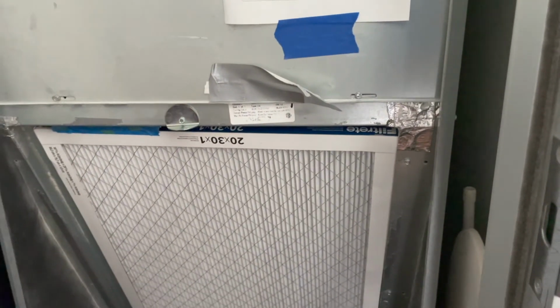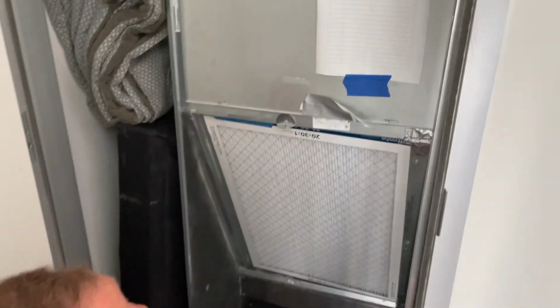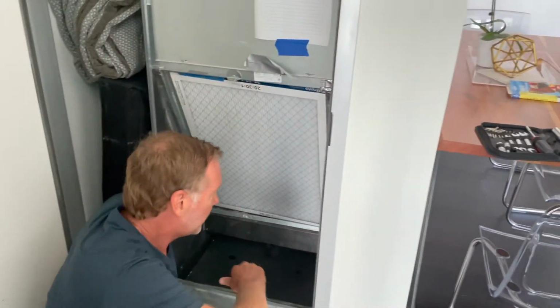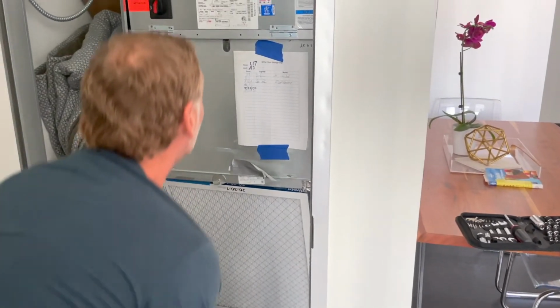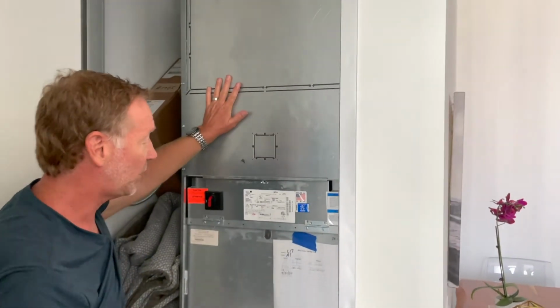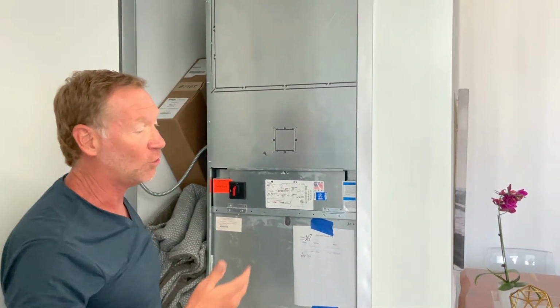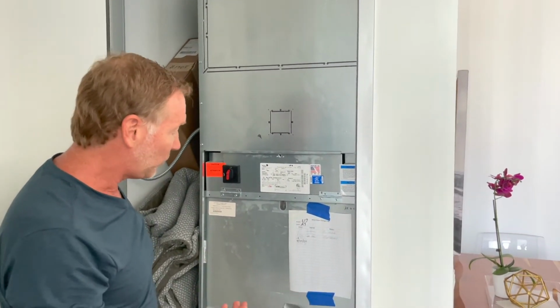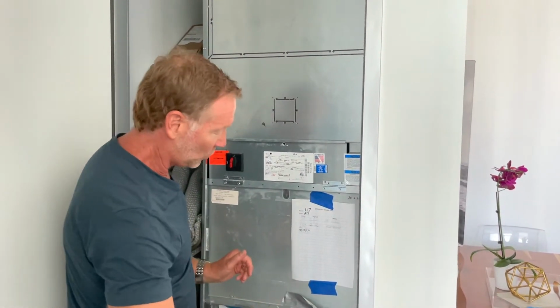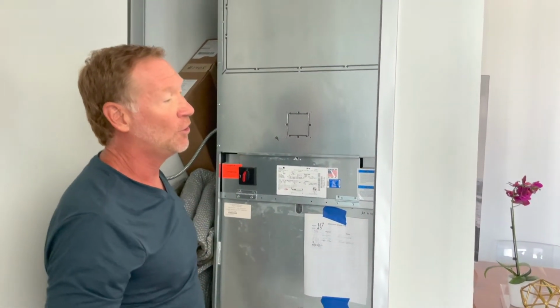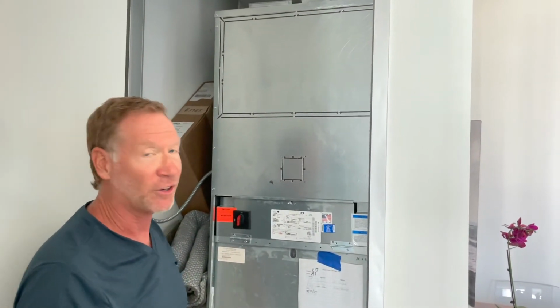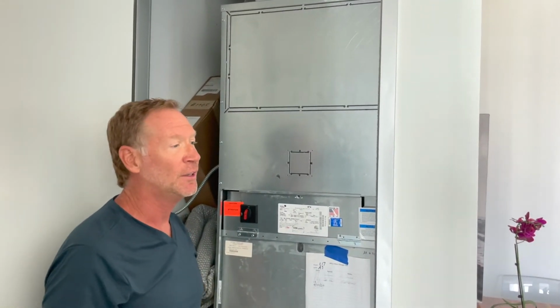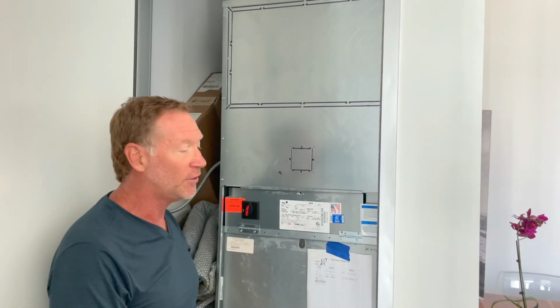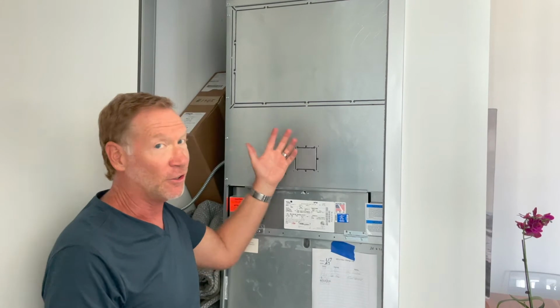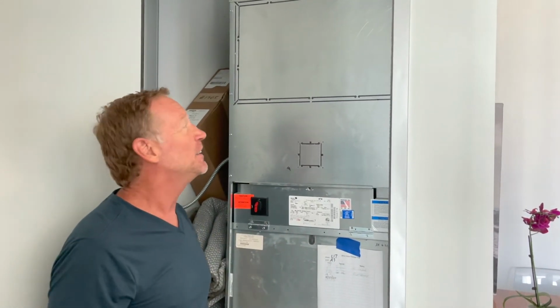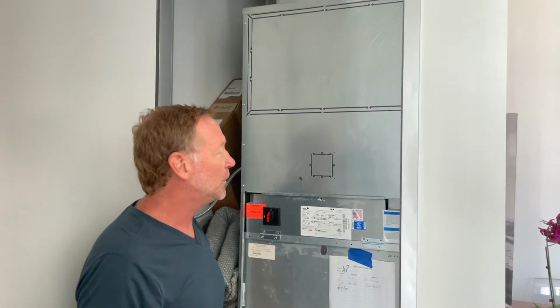The other thing a technician would do is measure differentials. Differentials mean how cold the air being produced is on the supply side versus the temperature going into the return. They measure that differential between what's coming in and what's coming out. For standard compressor condenser type units, that makes a lot of sense, because if the air coming in is 90 degrees, you're not going to have air coming out at 50 degrees. It's just impossible, not with the size of these units. So differentials don't really make sense here.